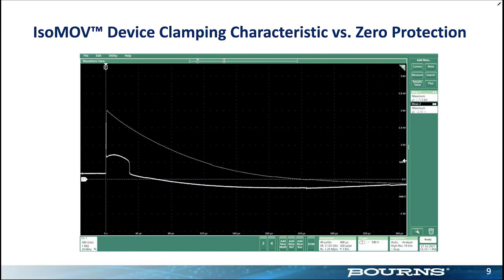So it's not a function of voltage, strictly speaking, but it's a function of how much energy is being injected into your circuit. So even though that spike on the front end may look scary, it really is not going to be a problem. We haven't had any issues with that. If you're familiar with GDTs, you're familiar with that, because that's a function of what the GDTs do. If you're not familiar with GDTs, rest assured that people have been using these for a long time. It won't be a problem.